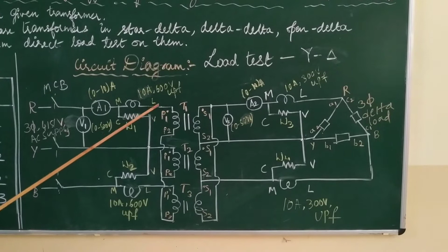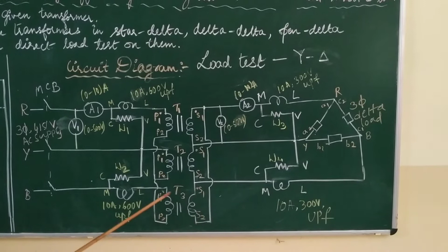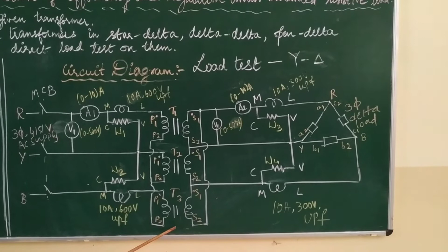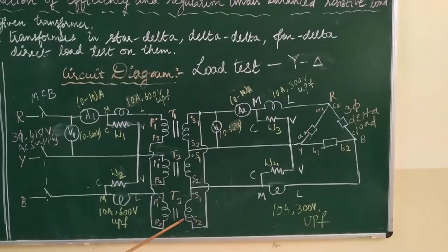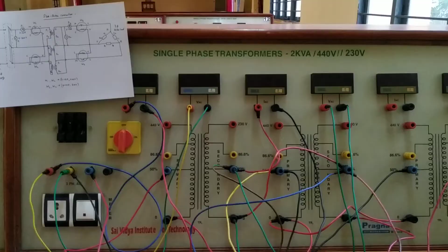along the primary, as I told just now, we have star connection. Along the secondary we are having delta connection. So in the setup whatever we have, we will be connecting the primary terminals at 50% tapping, and along the secondary also at 50% tapping. So the rating of the transformer that we are going to use here is 2 kVA transformer, 440 by 230 volts. Now let us go to the circuit connection.